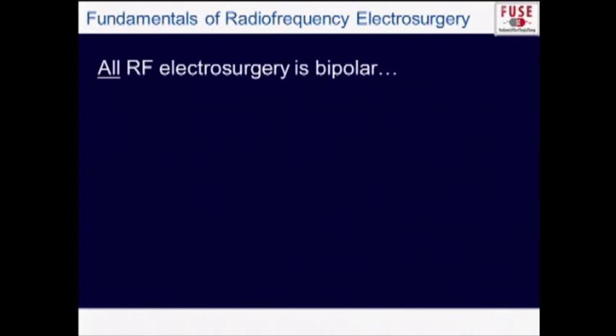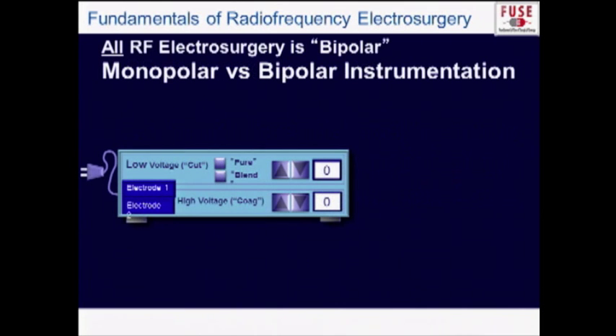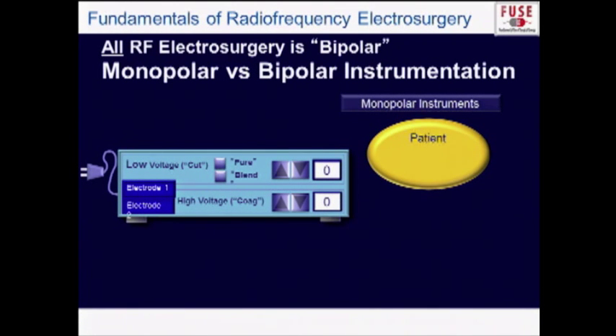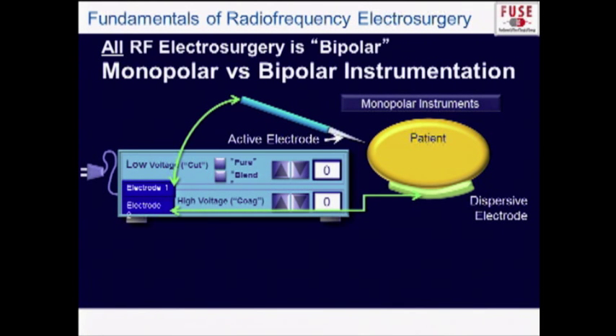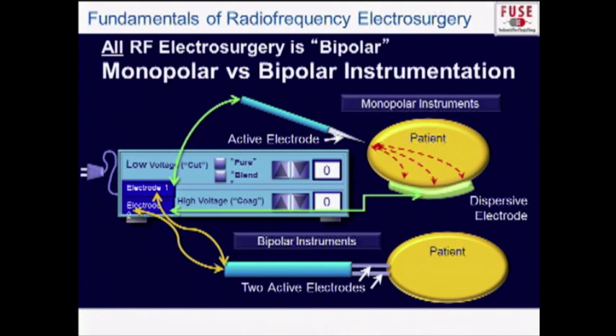All electrosurgery is bipolar — there's no such thing as monopolar electrosurgery because there are always two poles, two electrodes. What differentiates systems is the location and purpose of the second electrode. In a monopolar instrument setup, the active electrode is on the instrument and the dispersive electrode is placed on the patient — meaning the whole patient is interposed between the two electrodes, creating opportunity for current diversion. In a bipolar instrument, both electrodes are on the instrument, so only the tissue between the two jaws is involved.